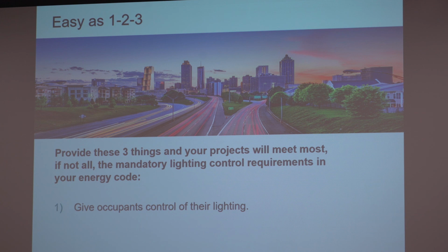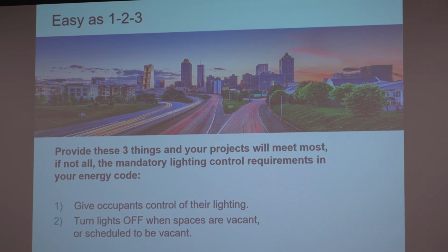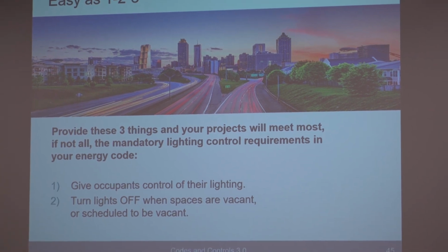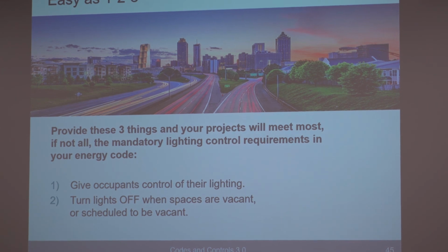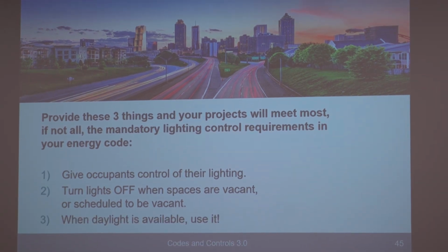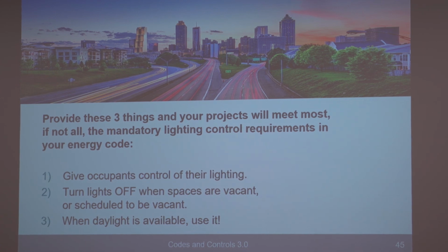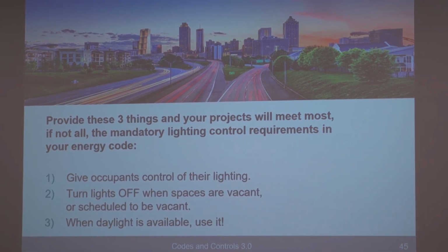So if you do these 3 things, you should meet nearly all, if not all, your lighting control requirements. Give occupants control of their lighting, in addition to just off and on. Give them at least another level. Turn lights off in spaces when they're vacant automatically or when they're scheduled to be vacant. And then lastly, when daylight is available from skylights and windows, use that to illuminate the space. Reduce electric light automatically in the daylight areas. You do these things and you should comply with nearly all, if not all, your control requirements.